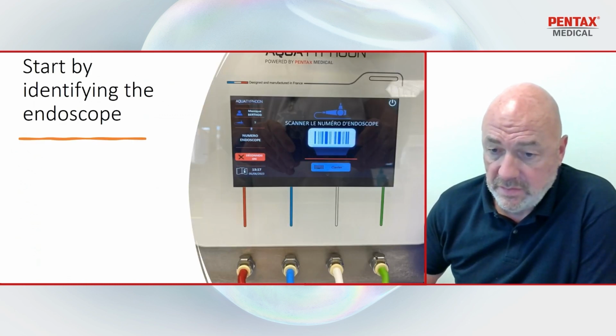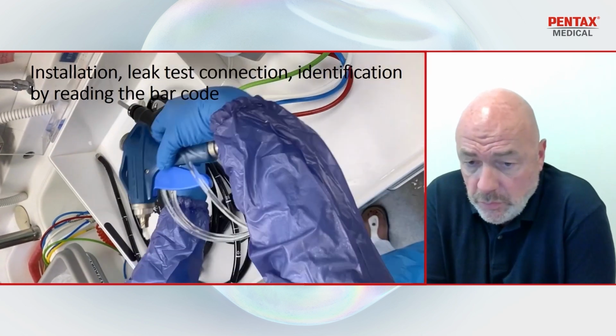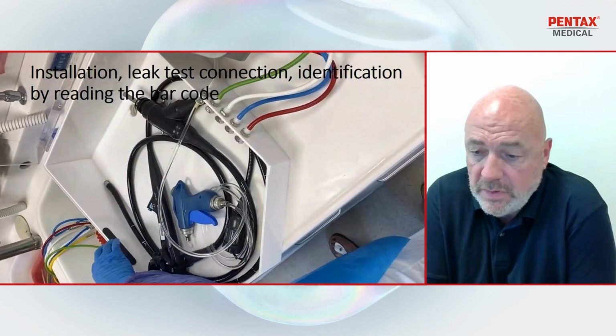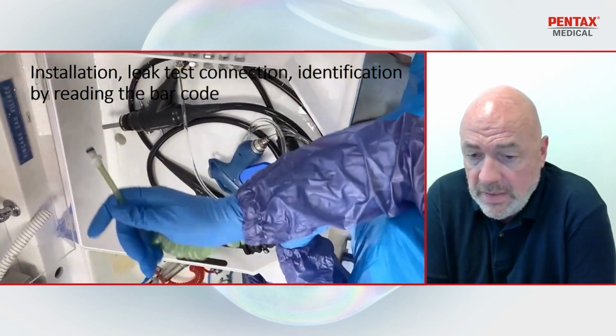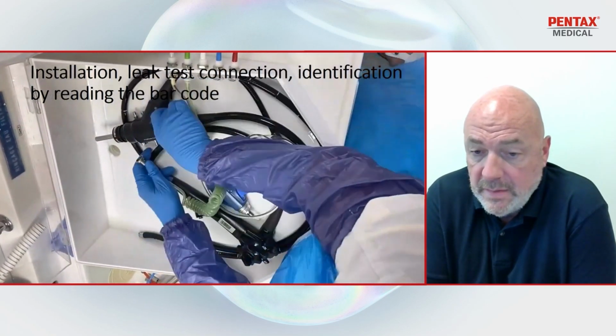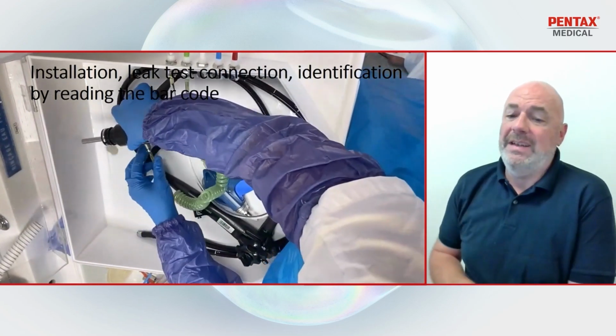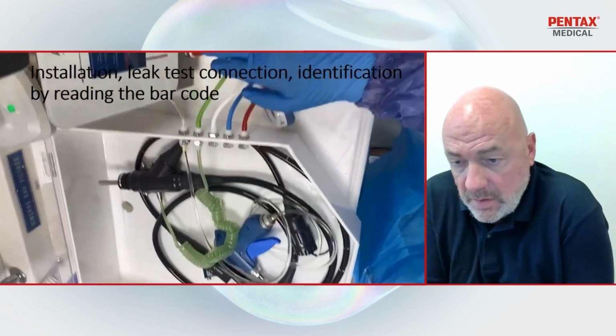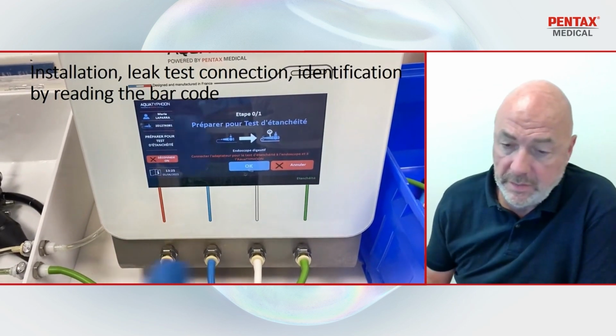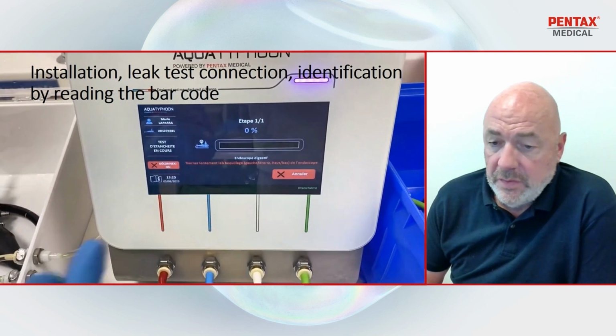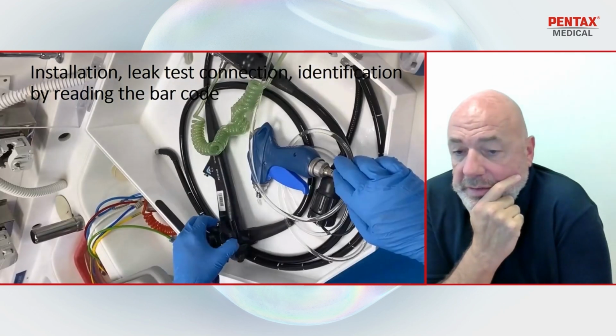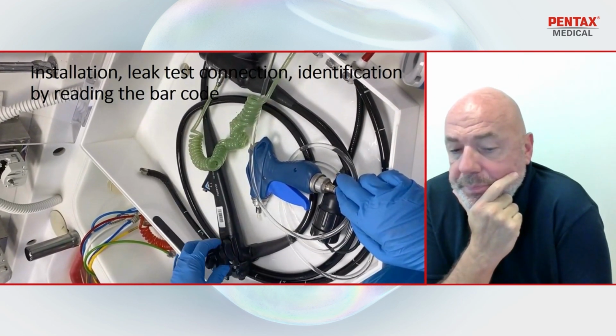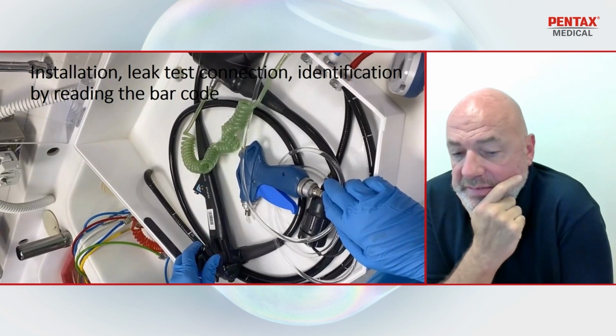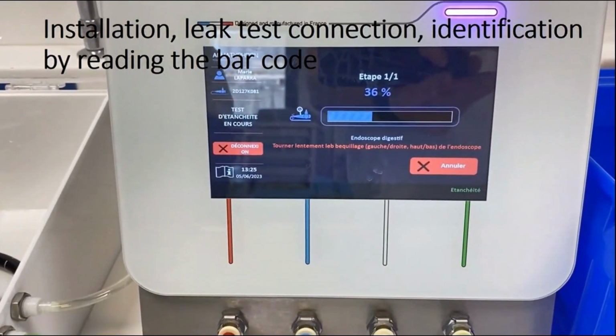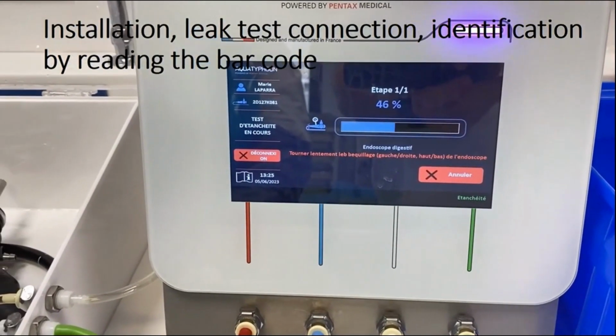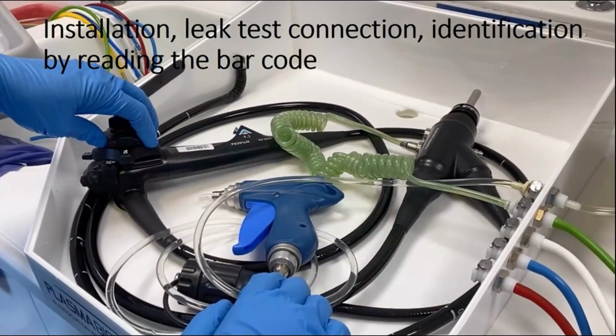What does the process look like? First of all, you start to identify the endoscope. As you can see in the movie, the first step is to put the scope in an Aqua Box in the Aqua Typhoon, which is designed by Plasmabiotics. The first step is the leak test connection in order to pressurize the endoscope, and after, the identification by reading the barcode. And after you make the leak test, this is a duodenoscope from Fuji. You can see when you want to make a good leak test, you have to move the scope right, left, up and down in order to see a leak.